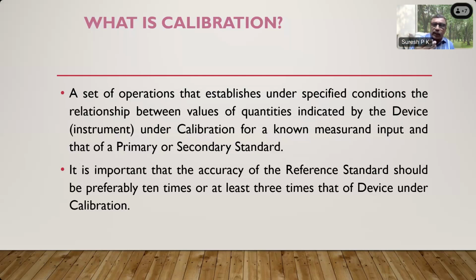So where is your interest? 24 hours you are operating. Out of 24 hours, if you are operating the flow meter at 50 meter cube per hour for 23 and a half hours, then your major interest is at 50 meter cube per hour. So you need to obtain the minimum error or the maximum accuracy at that particular flow rate. While doing the calibration, you have to ensure that you are getting maximum accuracy at your operating flow rate. If you concentrate on flow rates which are not in your operable area, that is not correct, because you compromise on the accuracy of the flow meter at the operating flow rate to attain accuracy at a flow rate at which you are not operating. So the flow rate at which you get the instrument calibrated, and the flow rate at which you concentrate on getting minimum error, is also important during calibration.